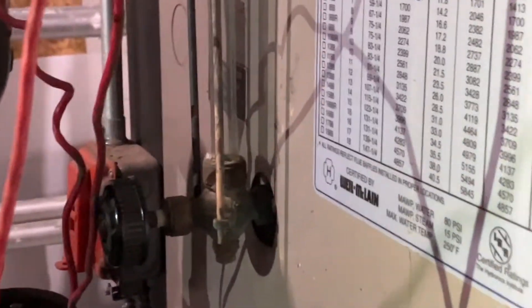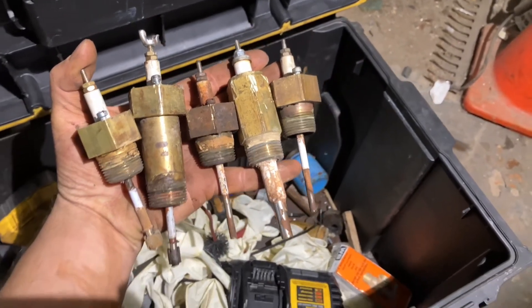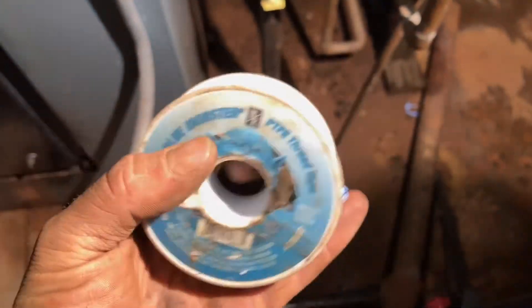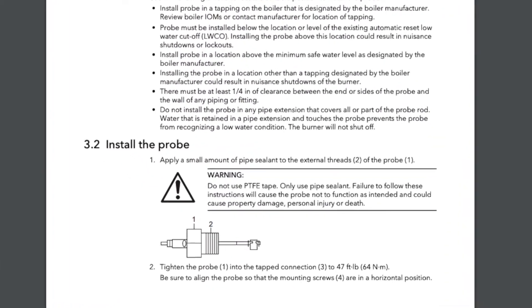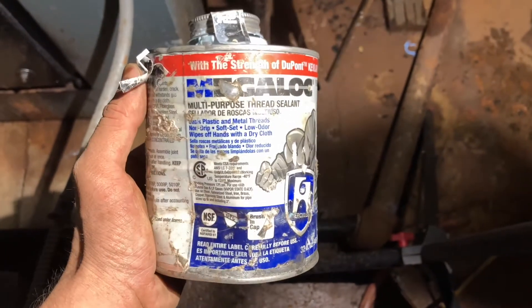That is why you will see me meticulously go through on every single tune-up, making sure the probe is cleaned. If it looks bad, replacing it. It should be checked yearly — it's not that difficult. A lot of times I've seen Teflon tape put on the threads to help put the probe in, and that can actually act as an insulative layer. So we always want to make sure we use Megaloc or any kind of pipe compound to secure the probe. It does not need Teflon.